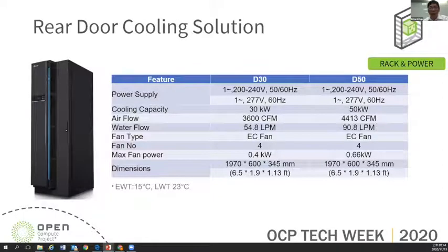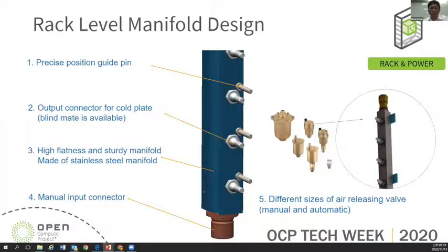The rear door heat exchanger we propose is 30 kilowatt and 50 kilowatt. This depends on how much heat is dissipated from air-cooled components. For manifold design, it comes with a hot swap primary connector for server online installation and maintenance. The manifold also has a guide pin for connector mating.